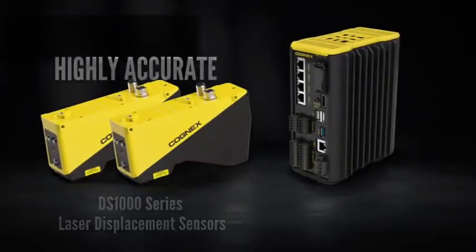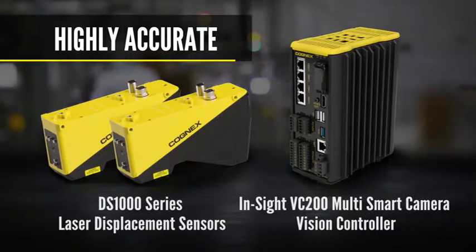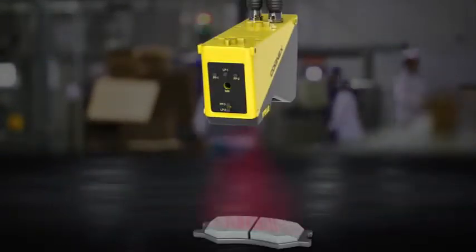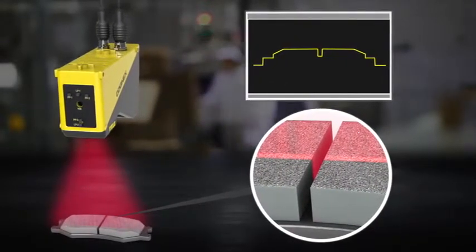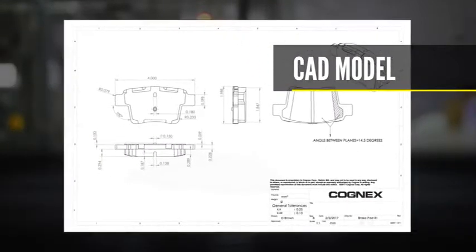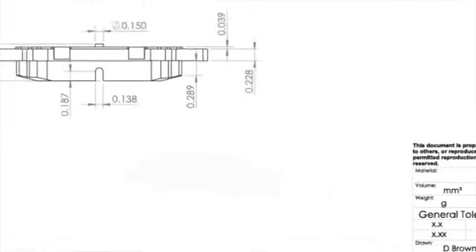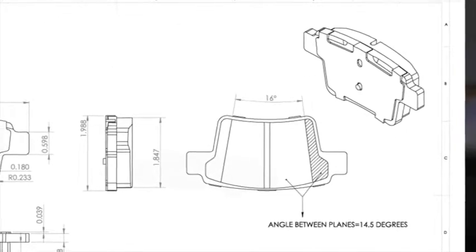The In-Sight Laser Profiler is a highly accurate measurement system used for verifying that a part's dimensions conform to the tolerances required by the part's design. A laser profiler works by projecting a laser line onto the surface of an object, creating a cross-section profile of the part's features. This cross-sectional profile can be viewed in the software interface. A CAD model of the part represents the critical dimensions which need to be measured. Using the extracted profile, the system analyzes the geometry to determine whether the object is dimensionally in tolerance and free of defects.